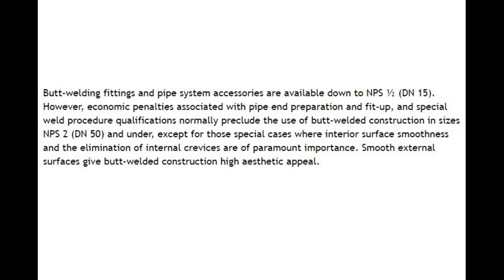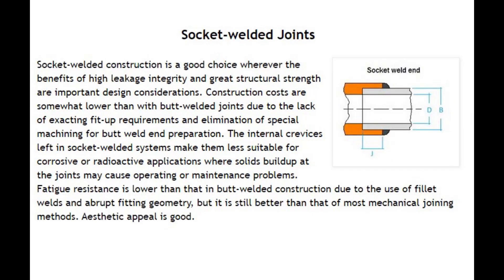Smooth external surfaces give butt welded construction high aesthetic appeal. Socket welded construction is a good choice wherever the benefits of high leakage integrity and great structural strength are important design considerations. Construction costs are somewhat lower than with butt welded joints due to the lack of exacting fit-up requirements and elimination of special machining for butt weld end preparation. The internal crevices left in socket welded systems make them less suitable for corrosive or radioactive applications. Fatigue resistance is lower than in butt welded construction due to the use of fillet welds and abrupt fitting geometry, but it is still better than that of most mechanical joining methods.